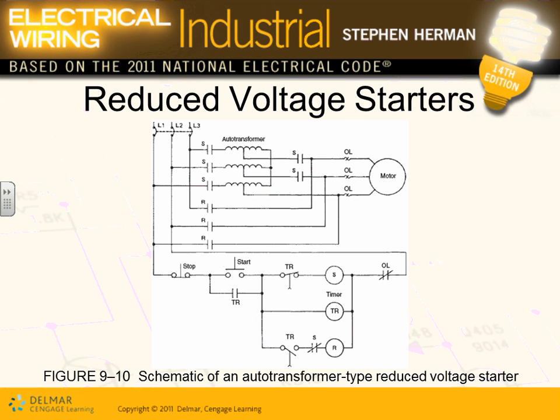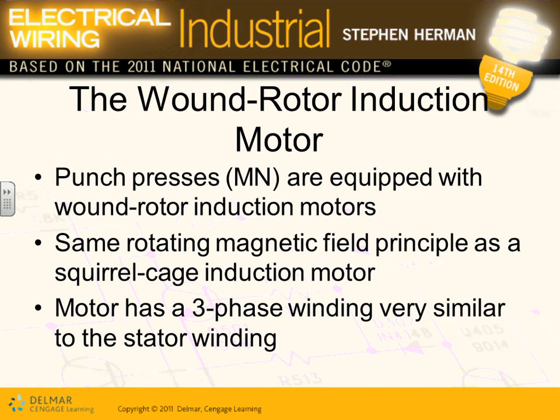Any questions? Any comments? Any questions about the reduced voltage start, as they call it? There are three ways: either resistor in series, or coil in series, or auto transformer. The ultimate solution, guys, reduce the voltage, start the motor gently. Then when the motor is up and running, raise the voltage so you can get the full potential, horsepower and torque out of your motor. Okay, so that's for the induction motor.